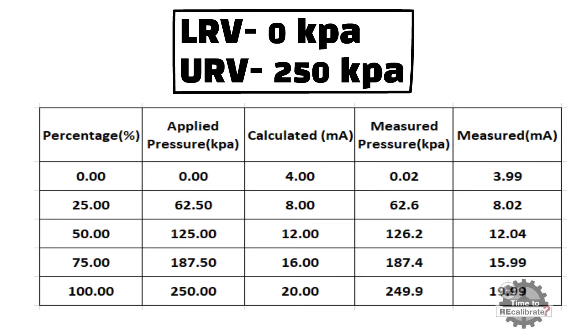At the end, apply 250 kPa pressure to the transmitter and note down the measured pressure value from the transmitter display. The measured pressure value should be nearest to 250 kPa. The measured milliampere value should be nearest to 20 milliampere. The five-point verification is done.